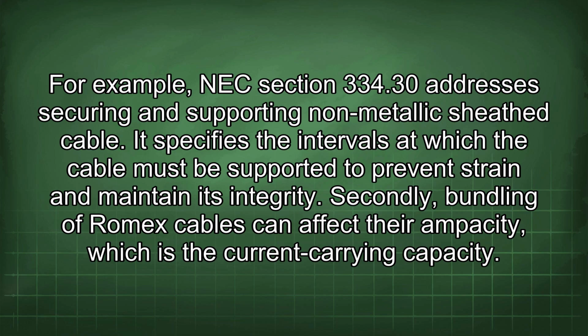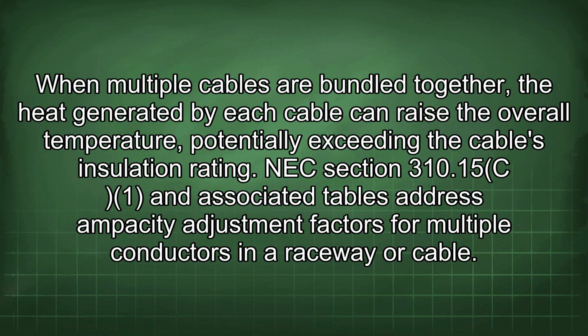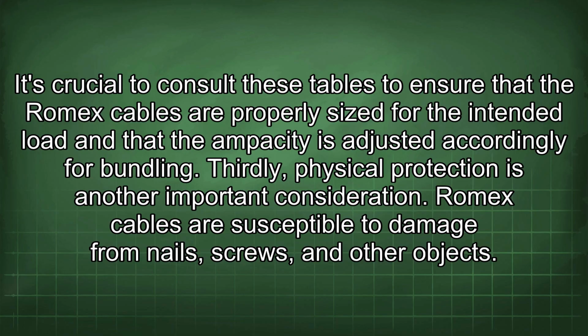Secondly, bundling of Romex cables can affect their ampacity, which is the current carrying capacity. When multiple cables are bundled together, the heat generated by each cable can raise the overall temperature, potentially exceeding the cable's insulation rating. NEC Section 310.15 and associated tables address ampacity adjustment factors for multiple conductors in a raceway or cable. It's crucial to consult these tables to ensure that the Romex cables are properly sized for the intended load and that the ampacity is adjusted accordingly for bundling.